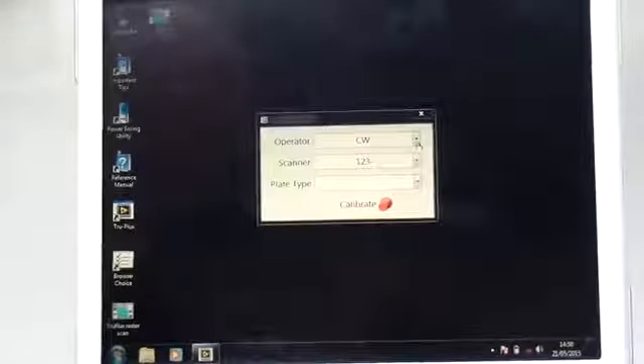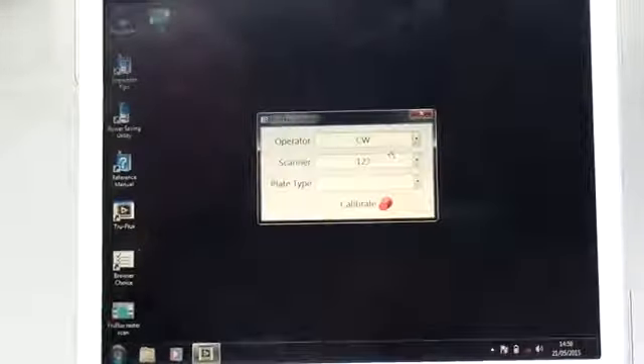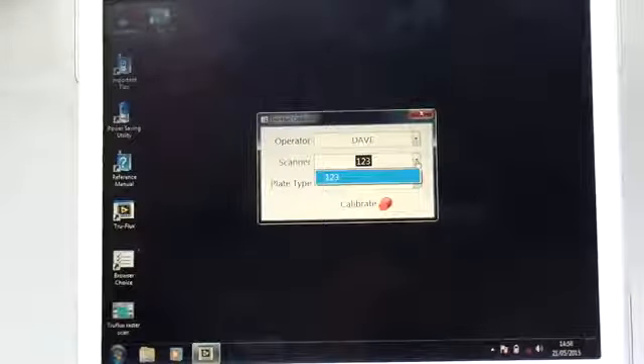Next stage is to select the operator who will perform the calibration and the subsequent inspection. You can select from a previously saved operator, or you can type the name of a new operator in, like so. You then choose the scanner which you wish to use with the laptop, because each scanner has to be calibrated, and then you choose the plate that you're going to inspect.